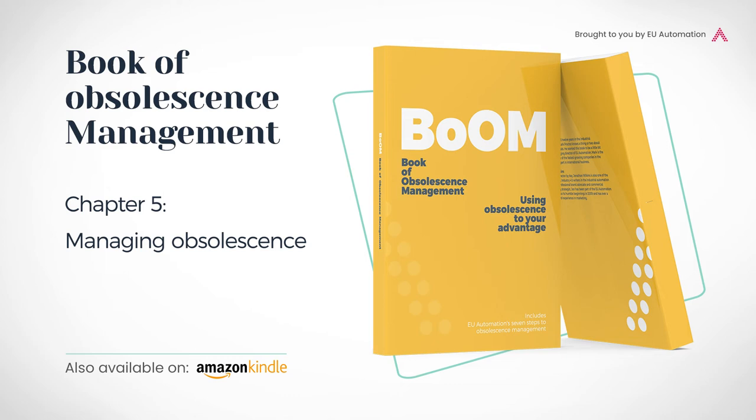Obsolescence management describes the process of identifying risks and planning preventative actions when parts, spares, equipment, people and software become obsolete. It is impossible to stop things becoming obsolete, but it is possible to mitigate the risks to production when they do. The basis of obsolescence management relies on life cycle forecasting and other analysis to identify the impact of obsolescence through all stages of a product's life cycle. Companies that invest in obsolescence management find different methods that suit them — hiring an obsolescence manager, employing third-party specialists, purchasing a computerized maintenance management system, or simply using spreadsheets to keep records of product life cycles. Obsolescence management boils down to these essentials: assess current systems and supply resources; conduct risk analysis on all components; prioritize risk; stockpile obsolete spares; record lead times and supply systems; ongoing review.